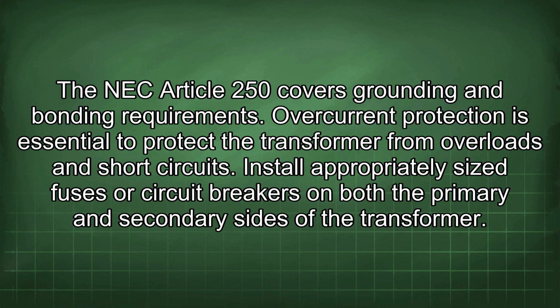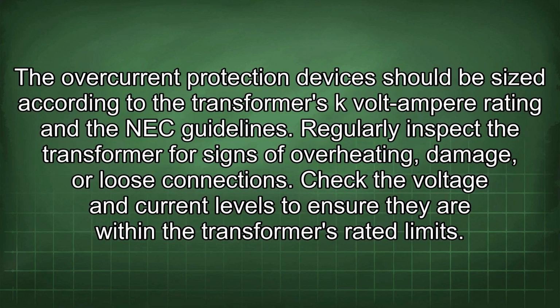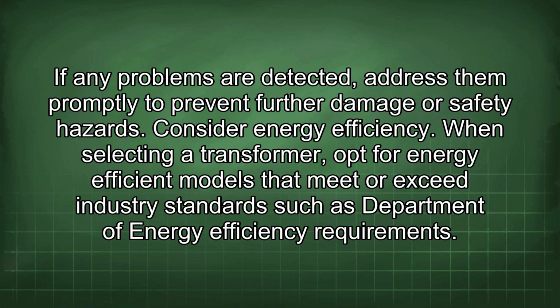Overcurrent protection is essential to protect the transformer from overloads and short circuits. Install appropriately sized fuses or circuit breakers on both the primary and secondary sides of the transformer. The overcurrent protection devices should be sized according to the transformer's kVA rating and the NEC guidelines. Regularly inspect the transformer for signs of overheating, damage, or loose connections. Check the voltage and current levels to ensure they are within the transformer's rated limits. If any problems are detected, address them promptly to prevent further damage or safety hazards.